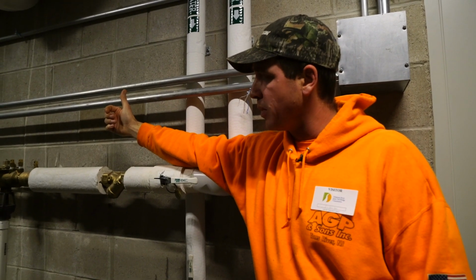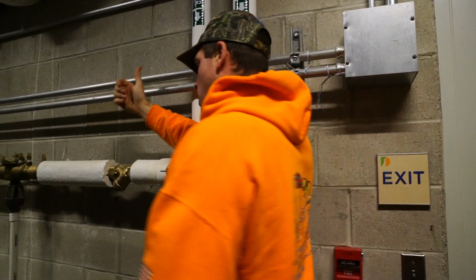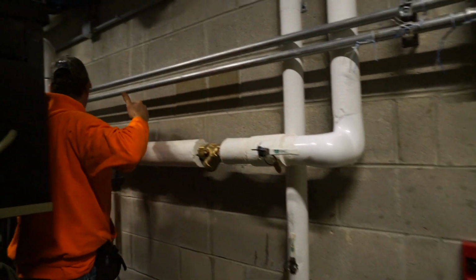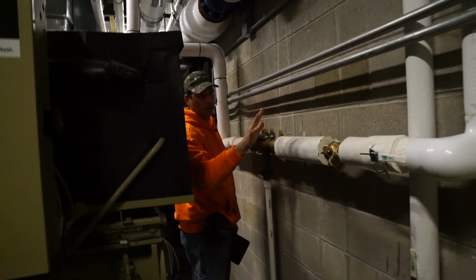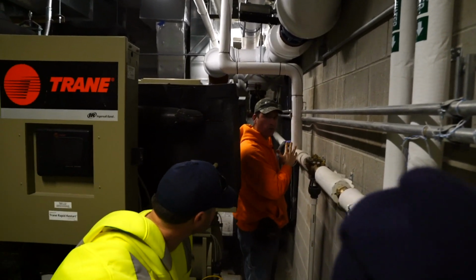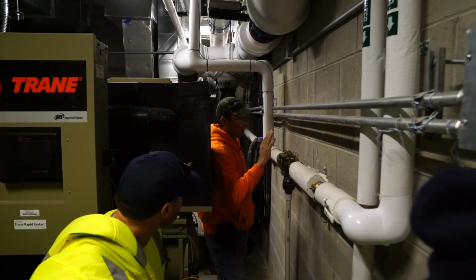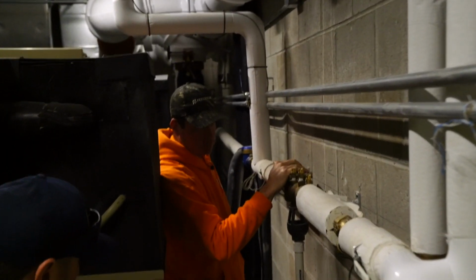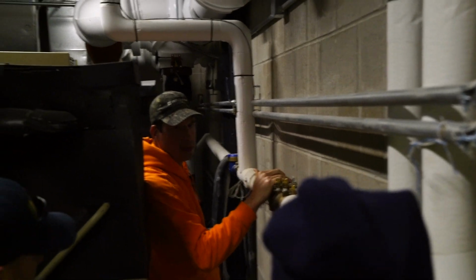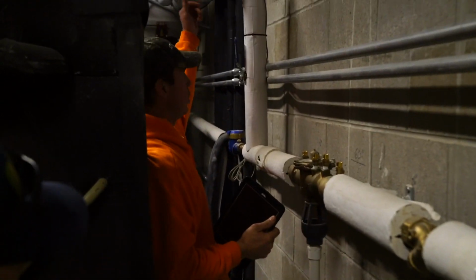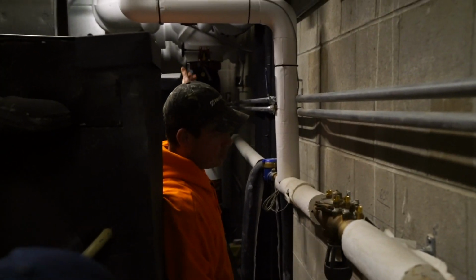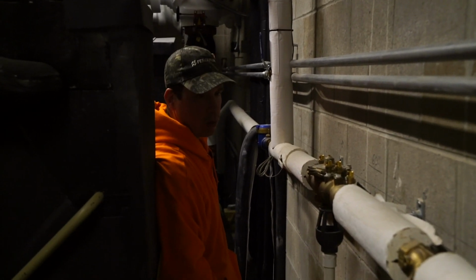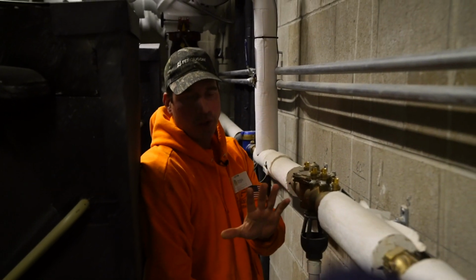As far as me with the plumbing contractor, my responsibility was from this backflow preventer back. After here, that was the HVAC contractor, all them. Now this is your backflow preventer. This stops cross-contamination in the building because if they have any chemicals, anything like that in the cooling tower, it will not backwash into the building.